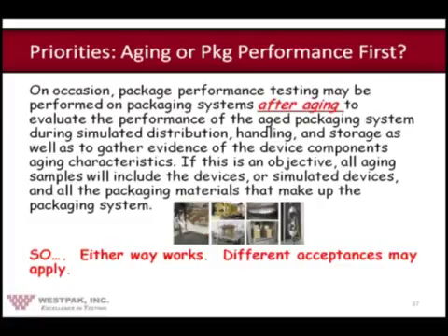The reality is, however, that the package performance testing may be conducted after aging, which would indicate storage of the product would occur at the manufacturer's location or some other location other than the customer's. It turns out that either way is acceptable. Acceptance criteria should be based on the package performance data conducted at the beginning of the aging studies.